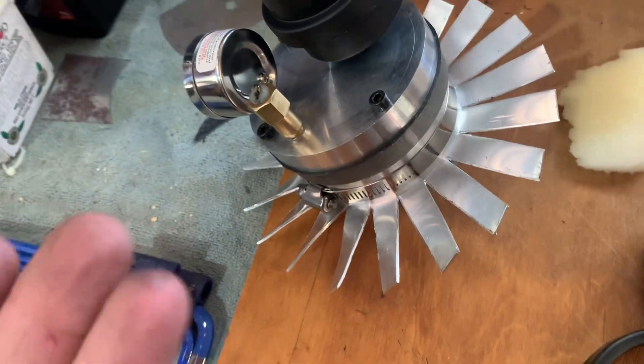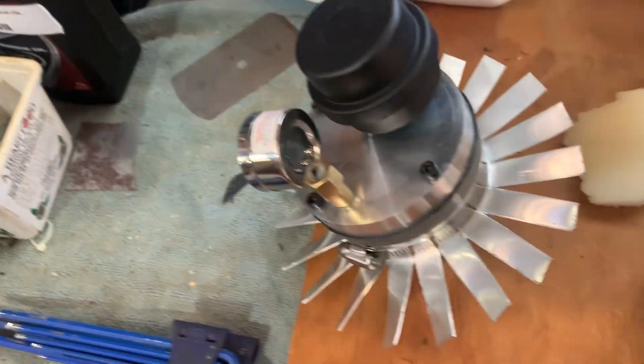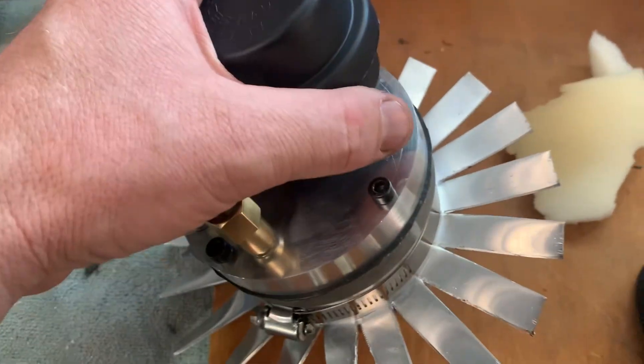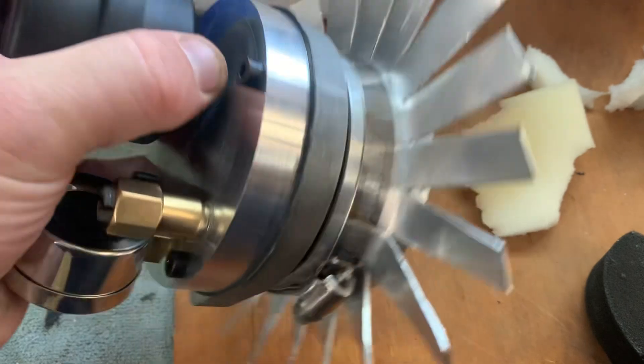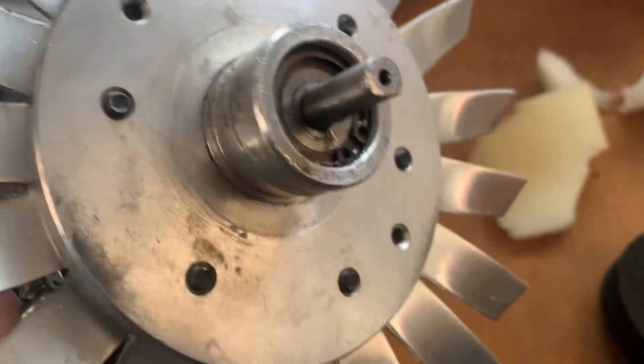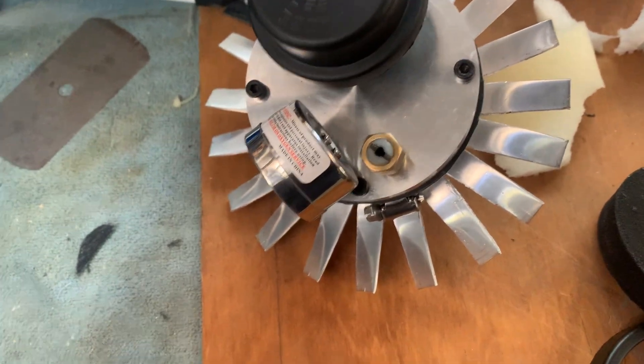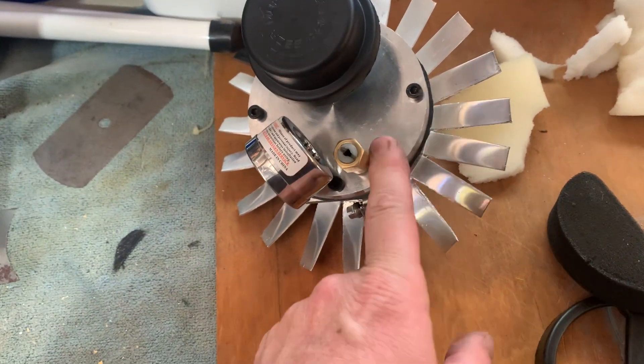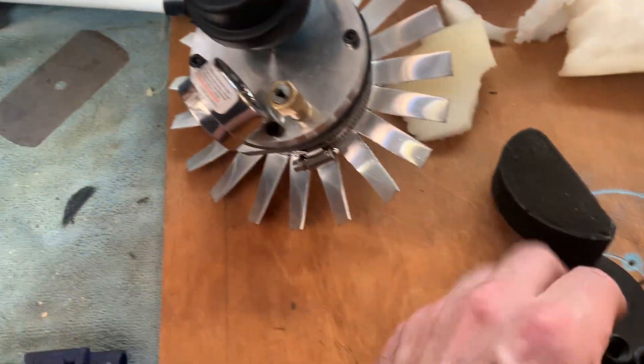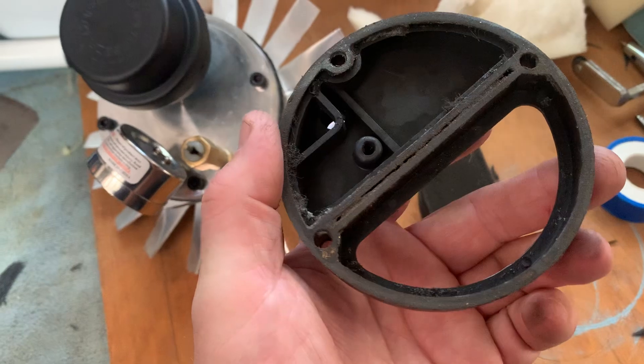They're a good burner from a design point of view — the actual unit itself looks good — but there are flaws, and we keep finding more all the time. This pump is the biggest Achilles heel we've come across so far. They should have had at least a cast aluminium version of this end cap straight from the factory.